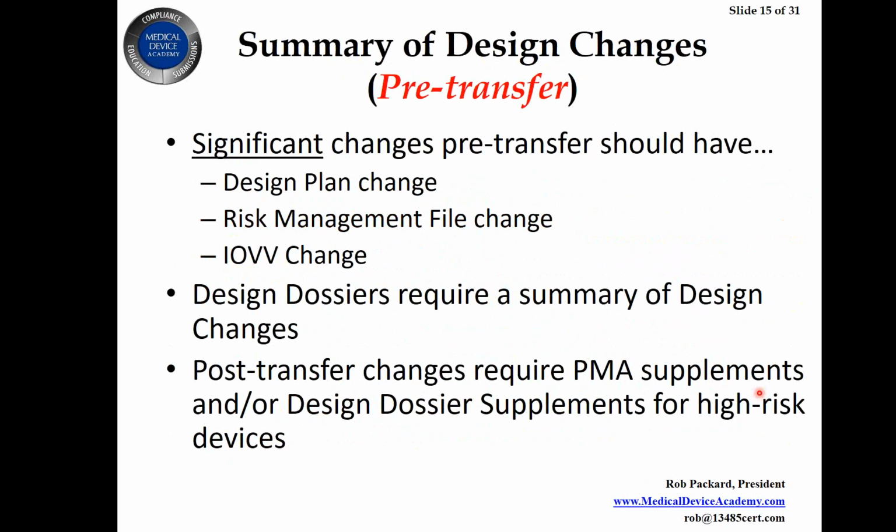For post-transfer changes, if you're going to have any changes to a PMA product, or you're going to have a design dossier, there are going to have to be supplements and verification validation documentation submitted and pre-approved by the regulator. So if it's a PMA, it's going to be FDA approval, and if it's a design dossier, it's a notified body. And this would be for the high-risk devices. So this is one of the reasons why, even if you have a clinical study, you really want this to be a 510K device rather than a PMA product. You don't want those PMA supplements.